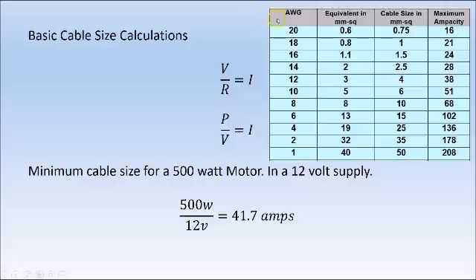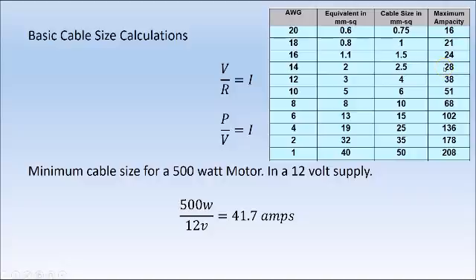A couple of points to note on the cable chart: AWG stands for American Wire Gauge — the larger the number, the smaller the cable. Then you've got a direct equivalent in millimeters squared, which is usually what we buy cable in in the UK. At the end of the chart is the maximum current carrying capacity for that cable. This is a generic table; these values will change depending on the rating of the insulation and the manufacturer themselves, as they determine the current carrying capacity.